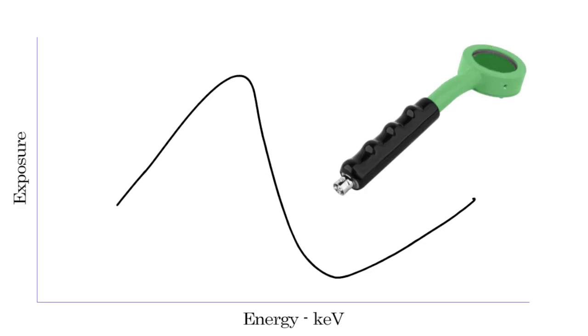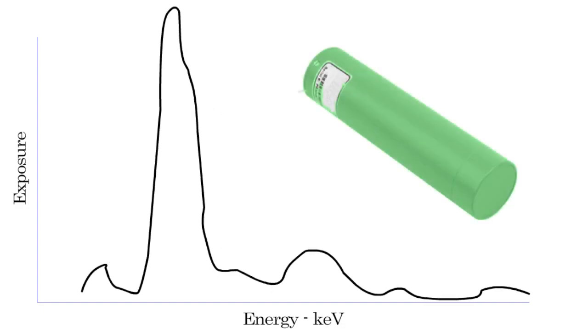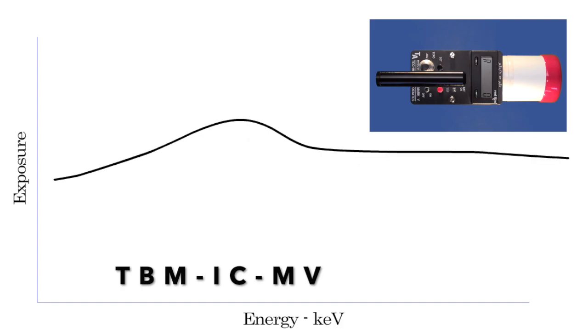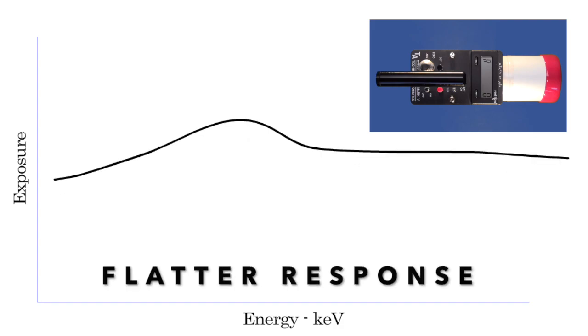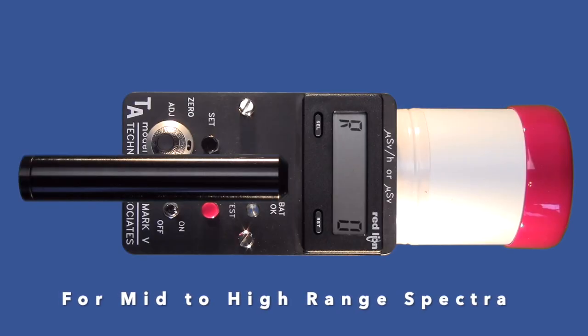Geiger-Mueller detectors can over-respond by up to 450%, and sodium iodide detectors can over-respond by up to 800%. Ion chambers such as the TBM IC Mk5 have a relatively flat energy response, providing a more accurate measurement of gamma x-rays in the mid-to-high range energy spectrum.